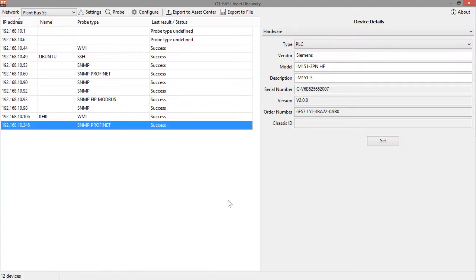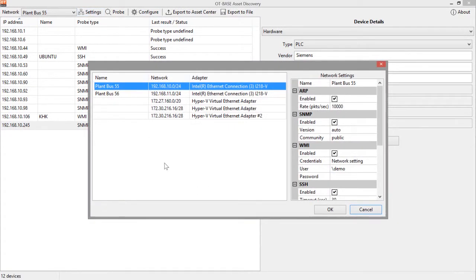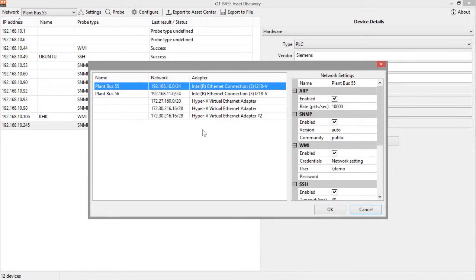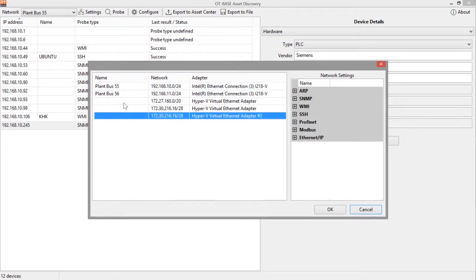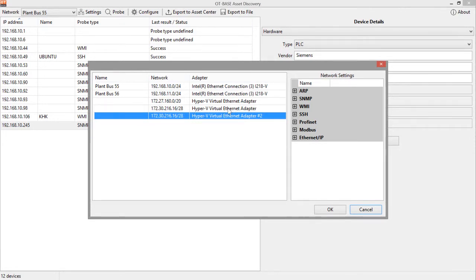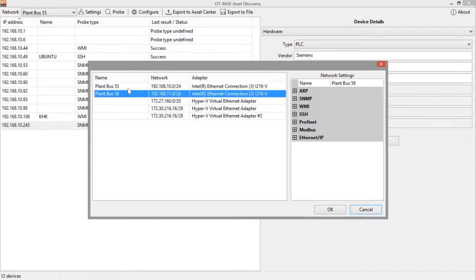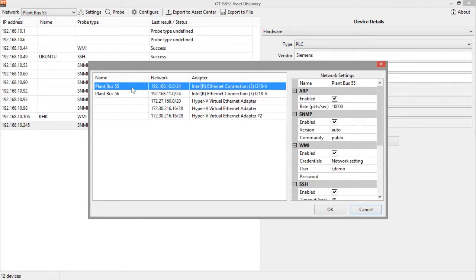There is one final setting that we need to worry about before we are done and that is in the network settings. Just remember you can use OT-BASE asset discovery for discovering multiple networks if the asset discovery node is connected to more than one network and what you have to do when using a full OT-BASE deployment every network needs to have a unique symbolic name such as PlantBus55 in our example. So this would not be a good idea. You cannot leave the name field empty unless you don't want to export data from these networks to the OT-BASE asset center. So if you don't set a name this data will not be exported. So in our configuration data from these two networks will be exported but again keep in mind that the name must be unique.